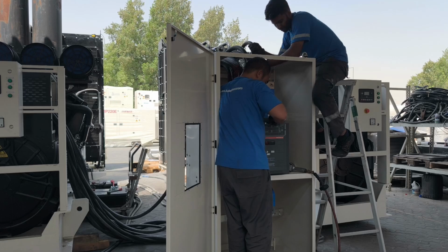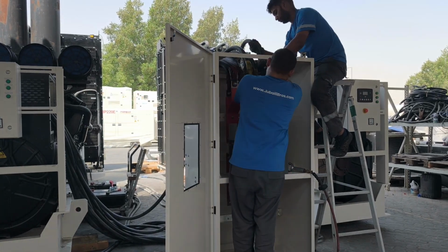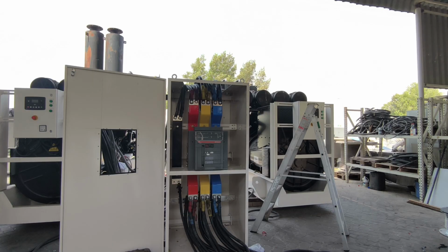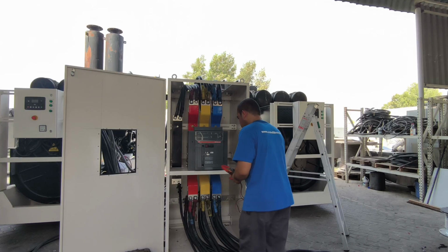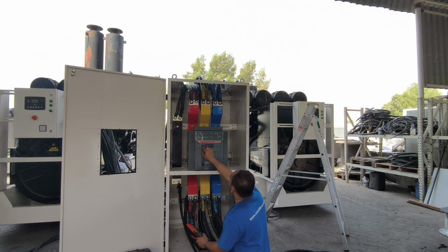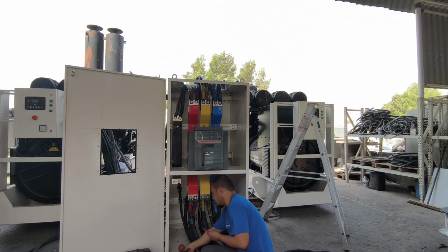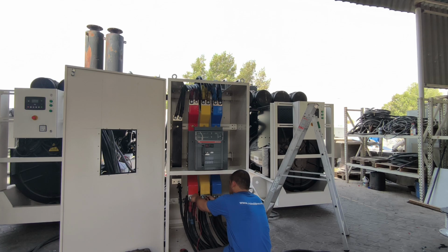By the way, on this side, this breaker is separated from our generator, and now we are connecting it. So this is how the finished connections look. We are ready for testing, but before that, we're going to double check those connections to see if we have any wrong connections or short circuits on the lines we are connecting. Even though there is some color coding, it's good to double check so we are assured we can do the tests with no failure during them.